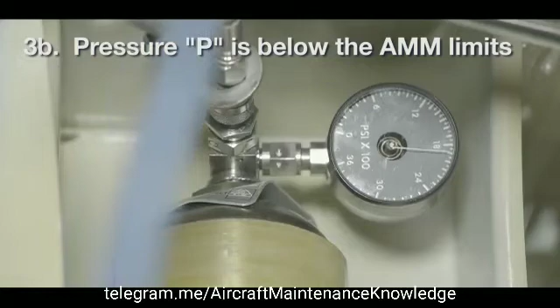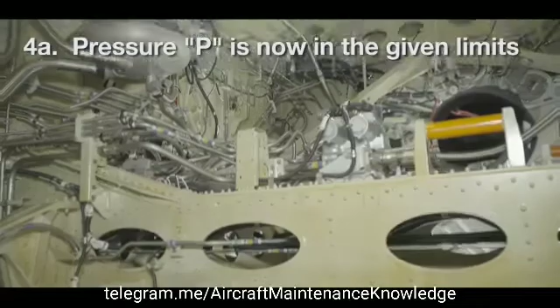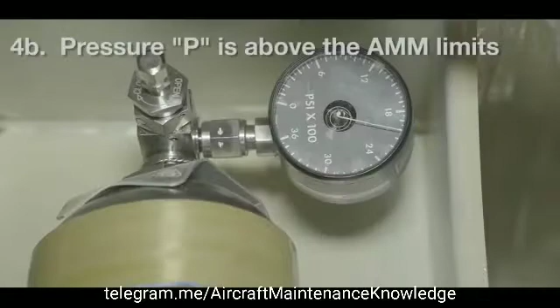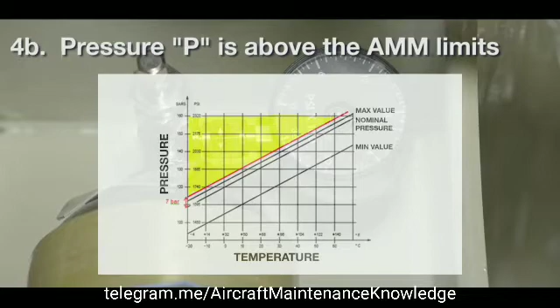Check the accumulator pressure after 20 minutes to ensure that there is no leak. If the pressure is plus or minus 7 bar, no more steps are necessary. If the pressure is still 7 bar or more above the nominal value, reduce the pressure to the nominal value.